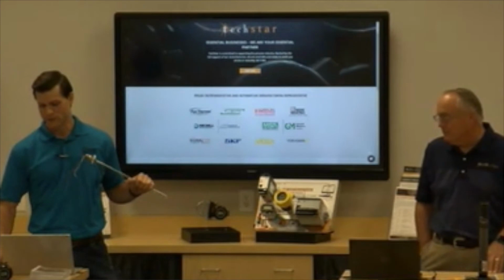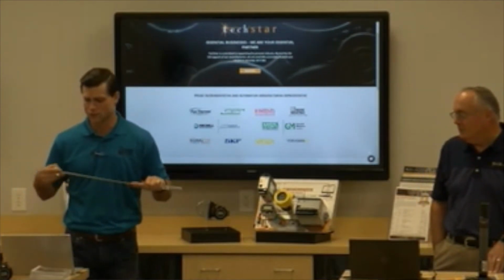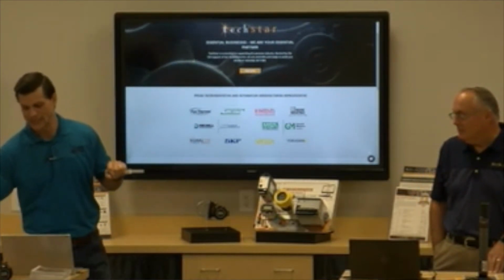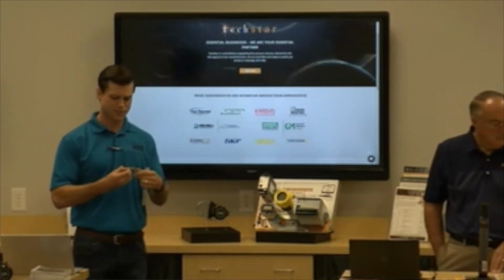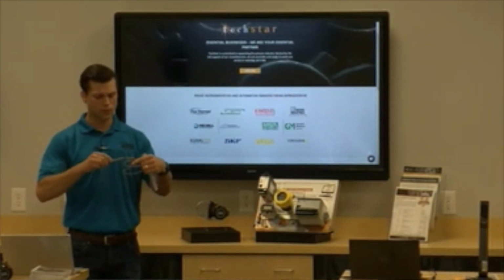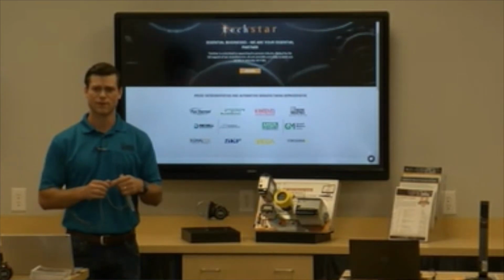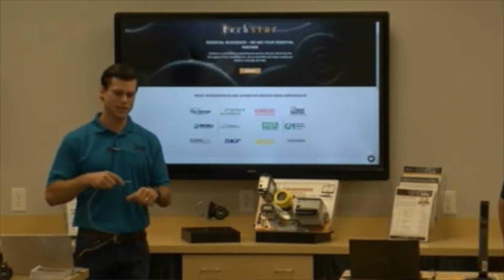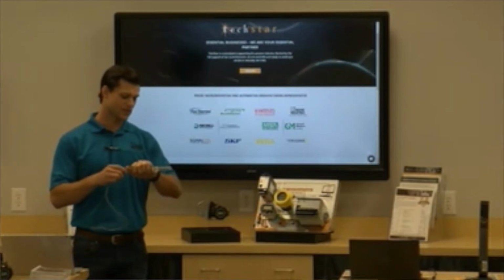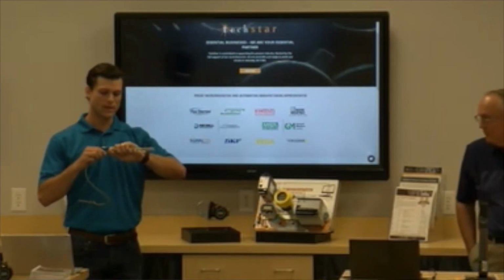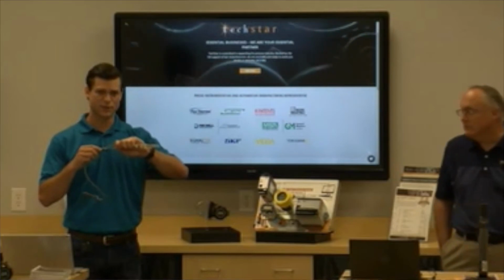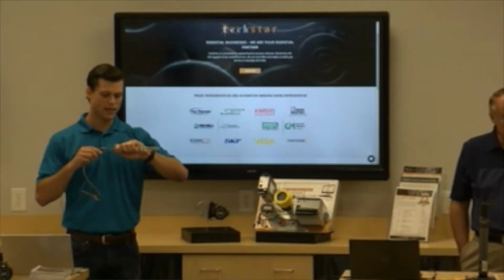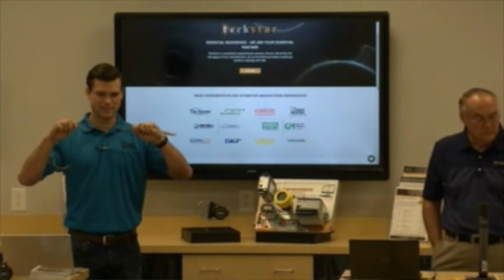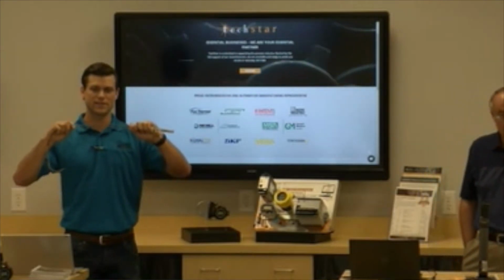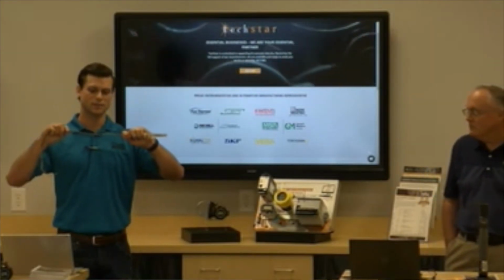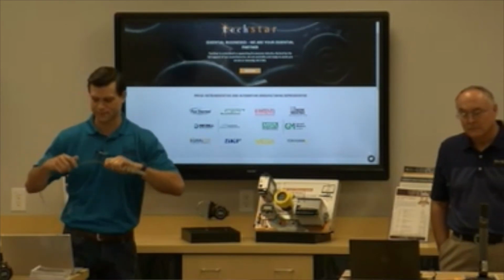So we have a solution to this, and our solution is very simply getting a temperature sensor, such as a worm, which I have here made by Moore Industries, but any temperature sensor that fits the process application needs. So with this specific sensor, we're able to insert the entire sensor into the thermal well, and we no longer have some existing portions outside that's in ambient conditions that's messing up the temperature measurement.